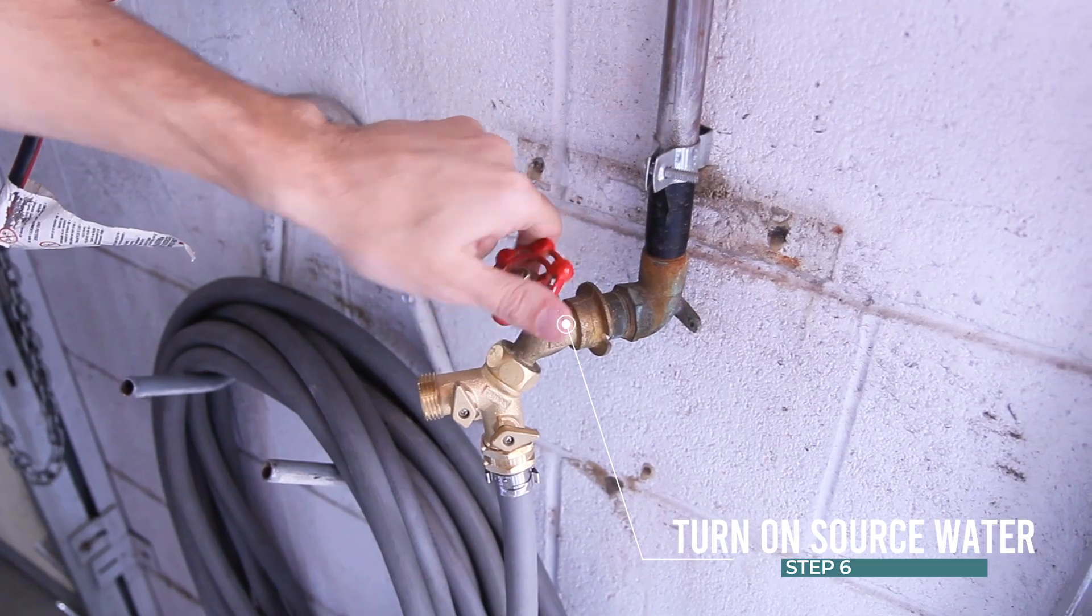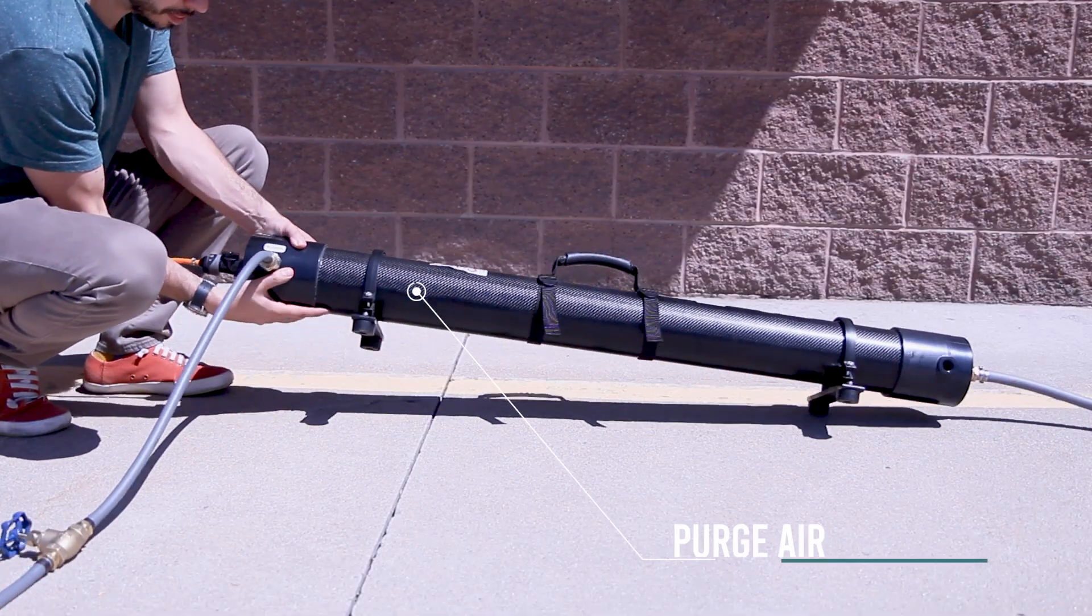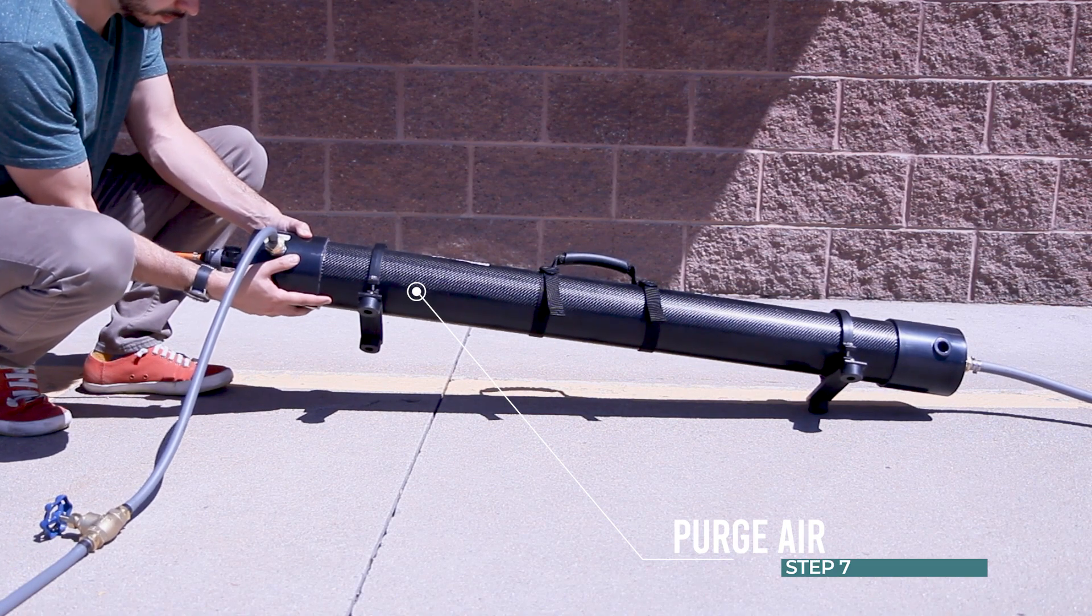Step 6: Turn on water. Step 7: Elevate the outlet side of the unit and rotate so bypass is facing upward until air has been purged from the RO housing through the bypass line.